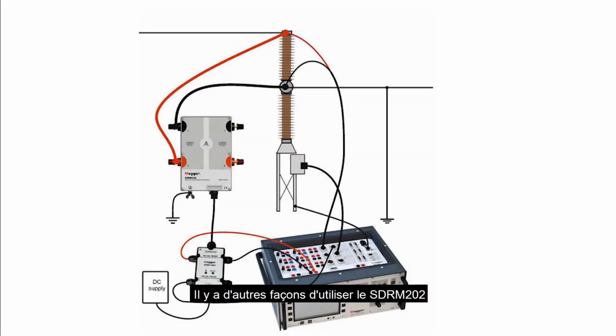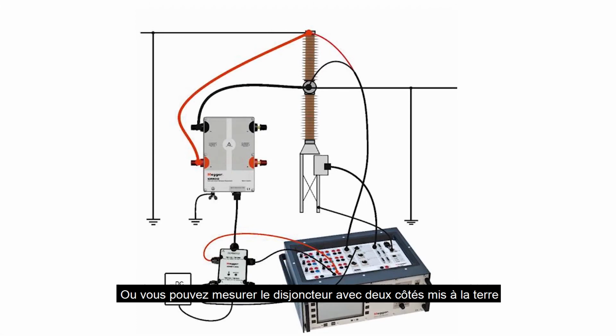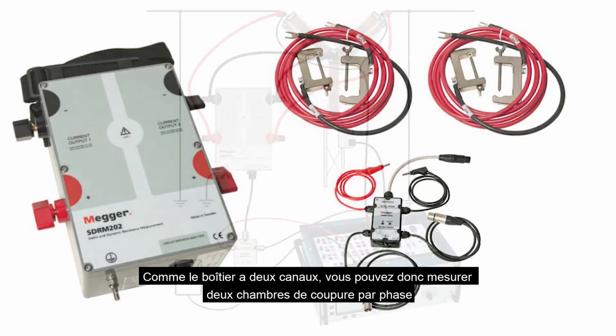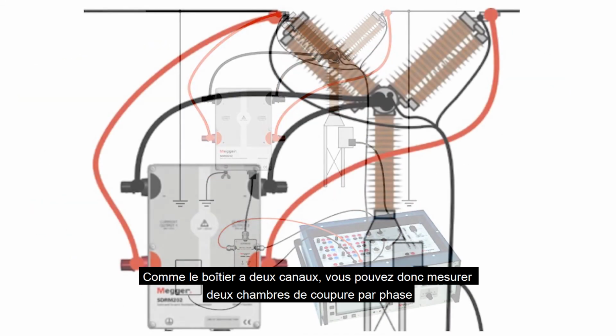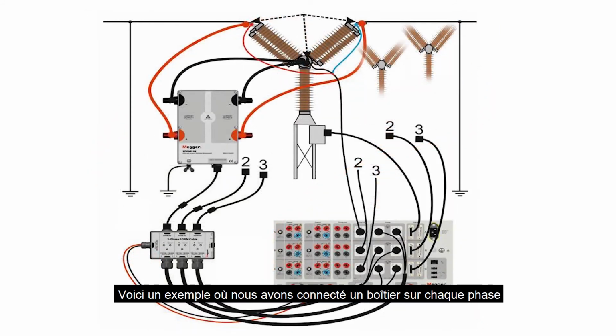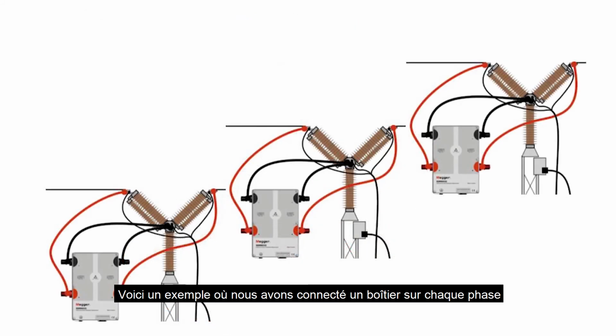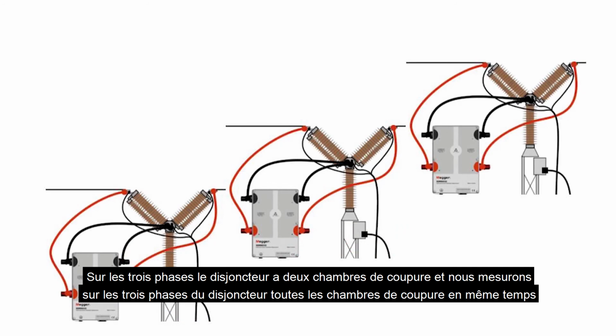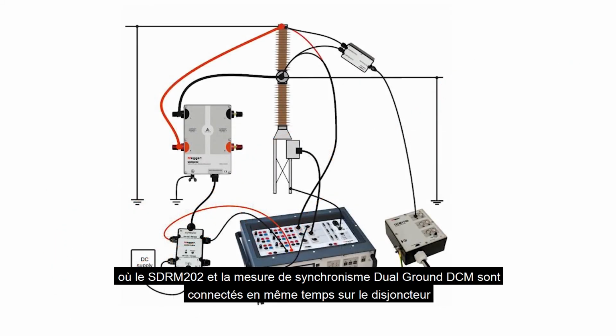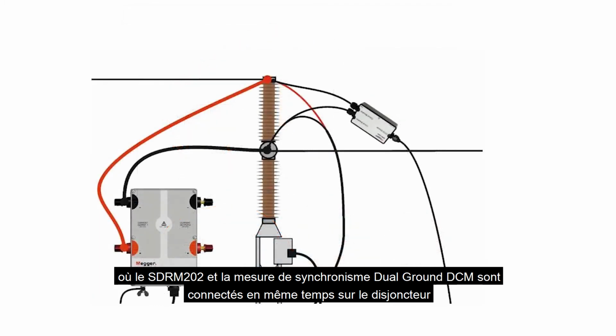There are other ways to use the SDRM202. You can measure the breaker with one side grounded, or you can measure with the circuit breaker 2 sides grounded. And the box has 2 channels, so you can measure 2 breaks per phase. Here is an example where we have connected one box on each phase on all 3 phases. The breaker has 2 breakpoints, and we measure this 3-phase breaker all breakpoints at the same time, 6 breakpoints in total. Or as we show here, where the SDRM202 and the dual ground timing, DCM, is connected at the same time on the circuit breaker.